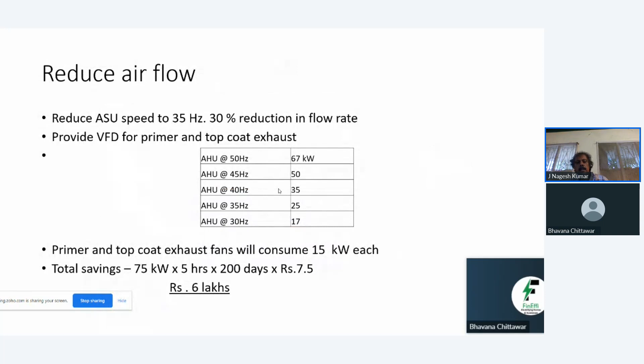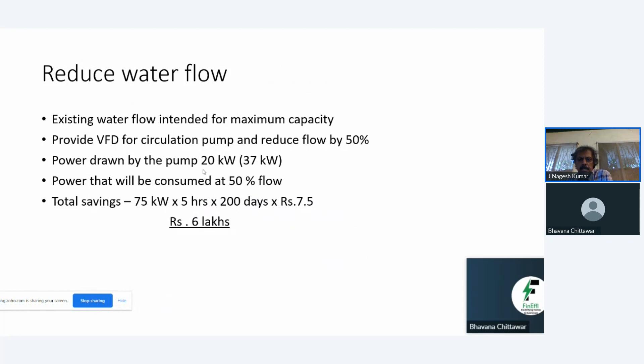At the same time, there is the circulating pump for absorbing the fumes. The air goes here, suppresses the fumes, gets into the water, and is then exhausted through the exhaust fans. So there's a pump circulating water for absorption of the fumes. As the fume generation is less, the water circulation also can be reduced. The pump is now operating at full flow. After a study with the existing throttle valve, we find that the flow can be reduced by 50%. So they need to later provide a VFD for this and reduce the speed. This is another major saving that they've been able to get.